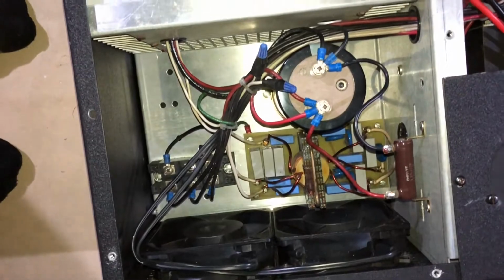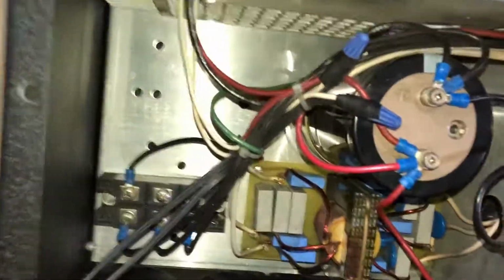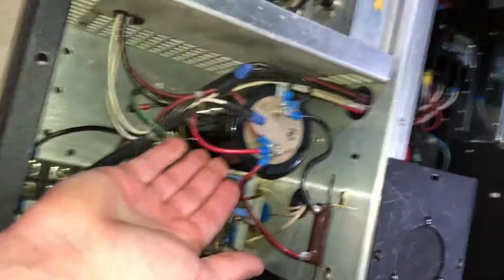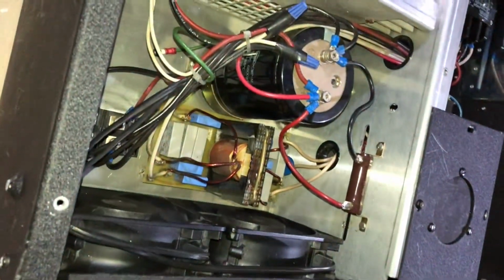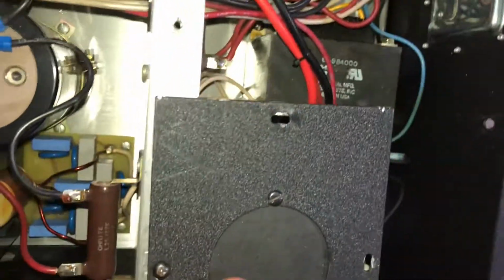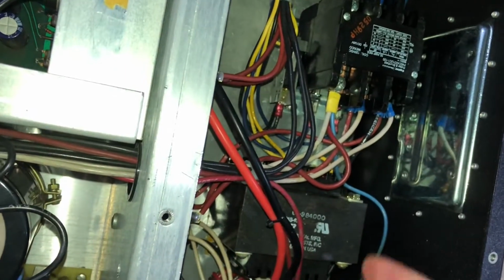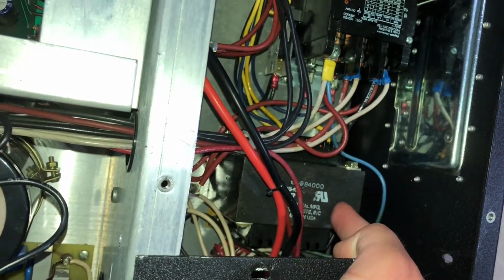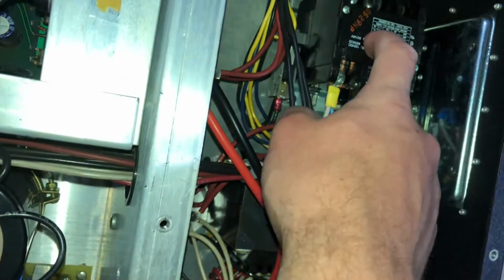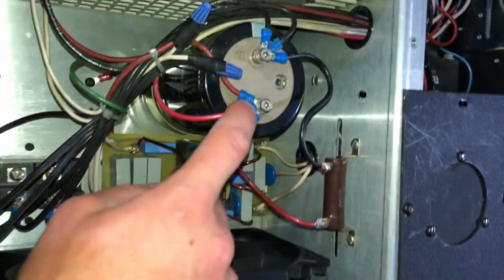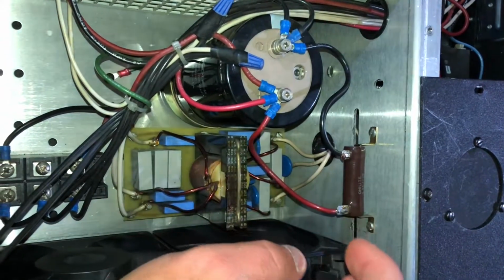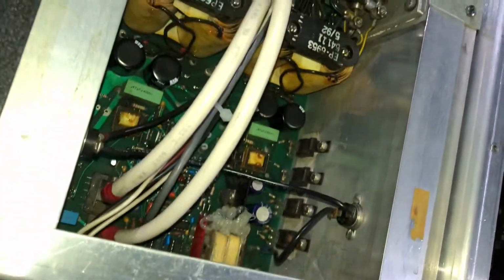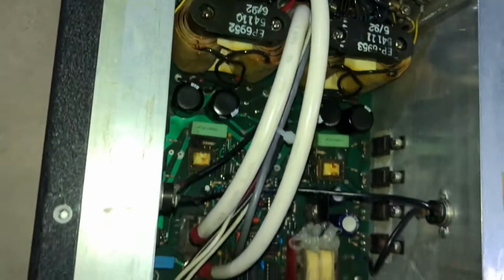Over here we have some rectification and a very large filter capacitor. Basically power comes in here, goes to the auxiliary transformer for powering the fans, and then when the contactor closes, sends power through here to this DC filtering circuit, which powers the switching power supply.